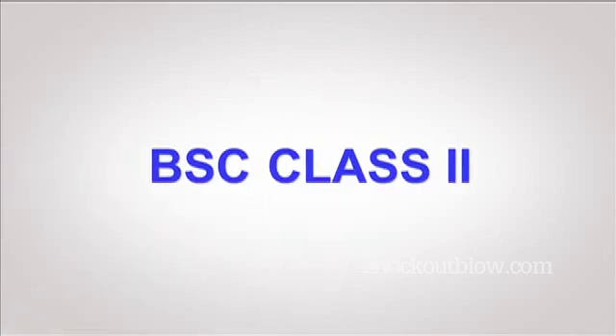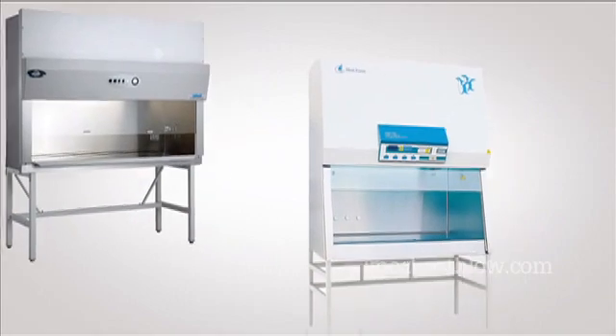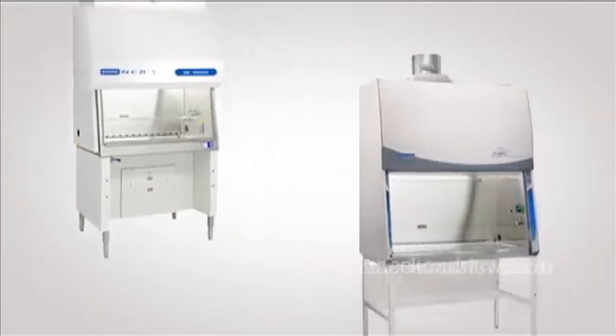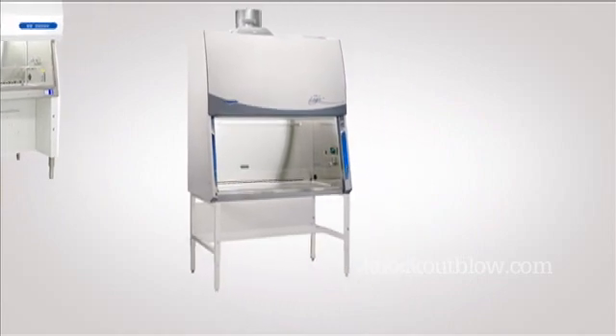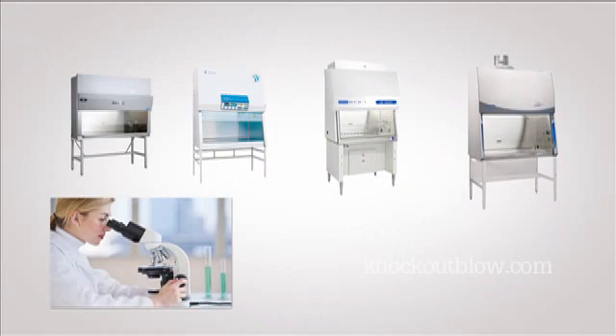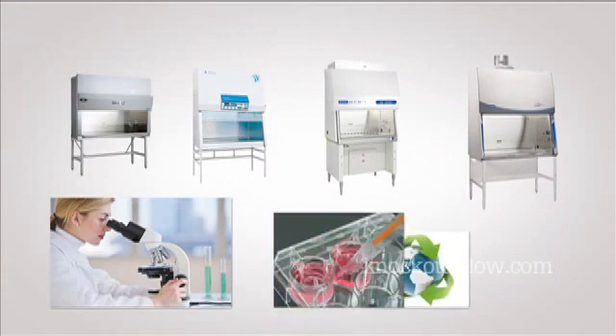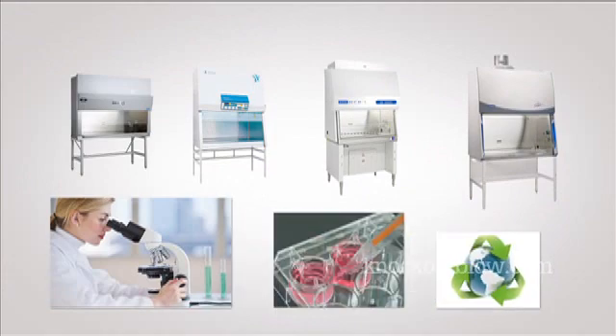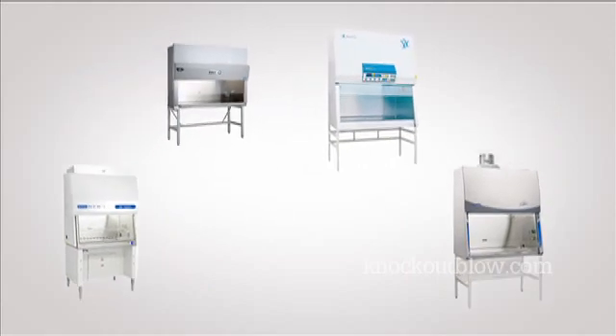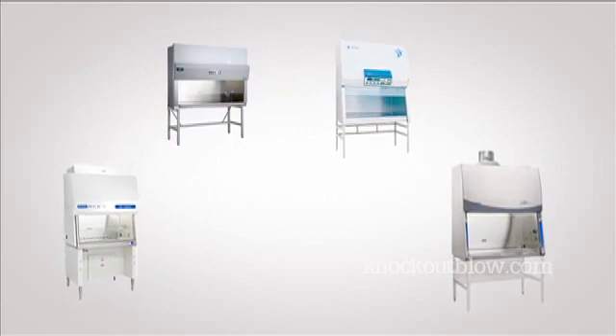Class 2: The BSC class 2 cabinet is the most commonly used for working with biological materials because it can provide all three types of protection: personnel, product, and environmental. BSC class 2s are classified into four subtypes: A1, A2, B1, and B2.